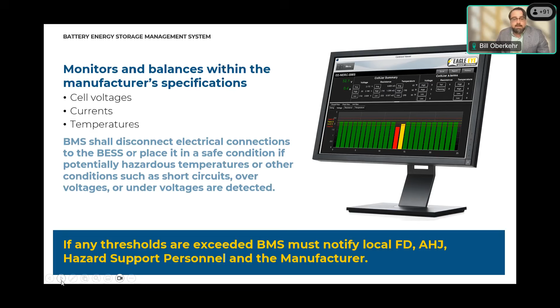The health of the energy storage system must be monitored 24/7 by a staffed facility. This is one of those fire safety working group recommendations that made its way into the 2025 code, based on the work FDNY had done in New York City. New York City has been requiring this remote monitoring system, remote monitoring center, or network operations center since back in 2019 -- again, that magical year for energy storage safety regulations, that watershed year. The fire safety working group looked at what New York City was already doing and the work FDNY had done and said, that makes a lot of sense. We're going to find a way to make this requirement apply statewide, and that's what you see here. So a 24/7 staffed remote operations facility to monitor that battery management system data is required by code, and folks submitting project applications should show proof of contracting or internal capabilities with a remote operations center.